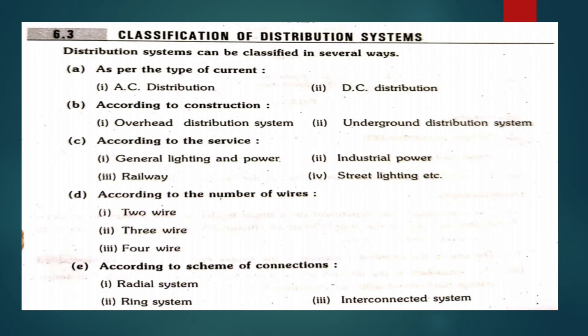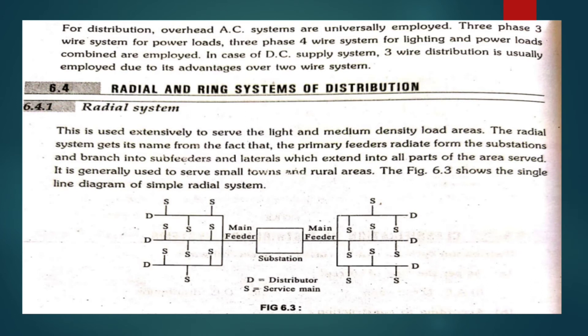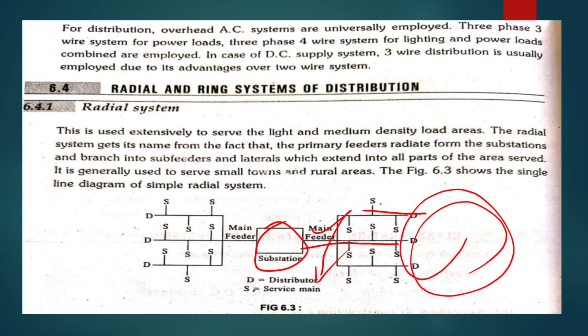First, the radial system. Radial means we have a substation with one path — main feeder, then distributor, then service mains — that means a single path. The total power is supplied from the top of this system. If there is a fault in the radial system, the total system will be affected. This is a drawback of the radial system.